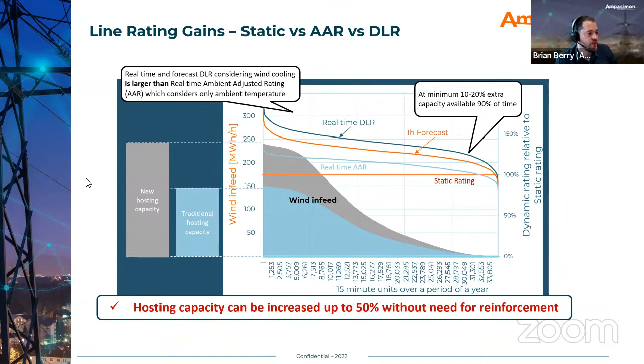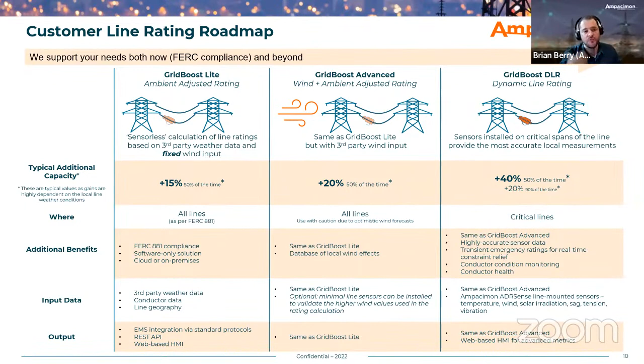So Ampacimon offers 3 solutions here. I'm not here to sell to you. I just use the slide because it's easy to explain. But we can do the ambient adjusted rating. We can do it with weather providers, but we can also do dynamic line rating with sensors on the line. And as I say, going from an ambient adjusted rating can give you plus 10 to 15%, whereas dynamic line rating with a sensor on the line can give you up to 40% extra. Enough about that. So here's our cool technology.